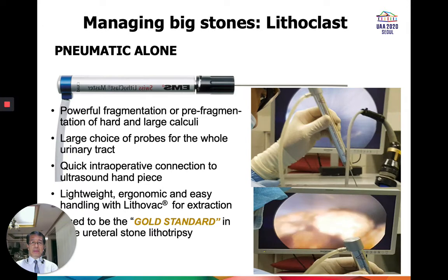The pneumatic system alone provides powerful fragmentation, or pre-fragmentation, of hard and big stones. With a wide range of probes of different sizes, it is a safe alternative for intracorporeal lithotripsy for large ureteral stones and was considered the standard before the arrival of the holmium laser. The probe is lightweight, ergonomic, and easy to handle. Switching and connection to the ultrasonic device to provide combination ICL is easy.